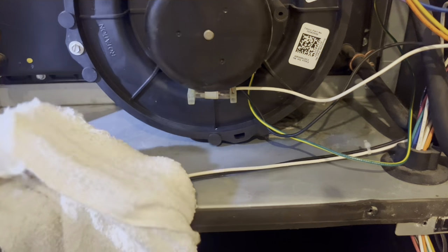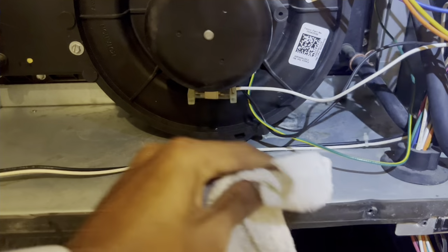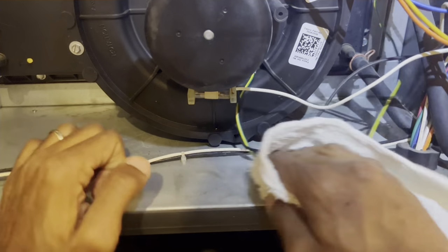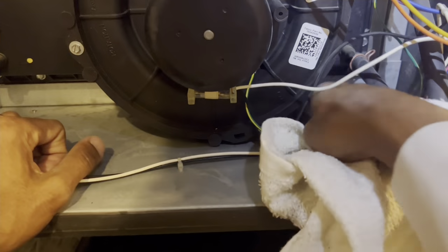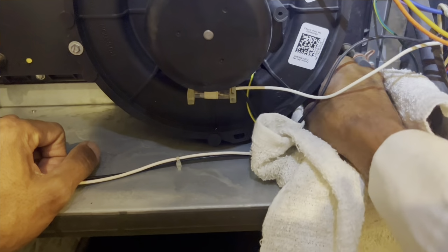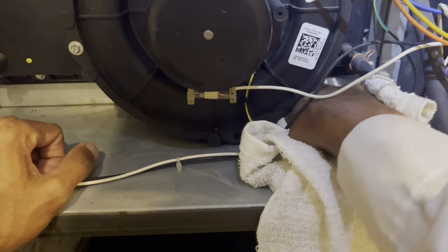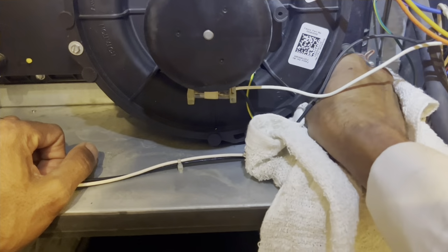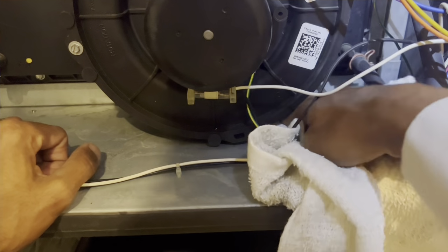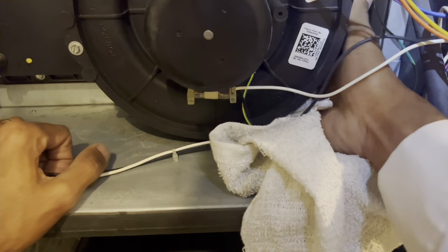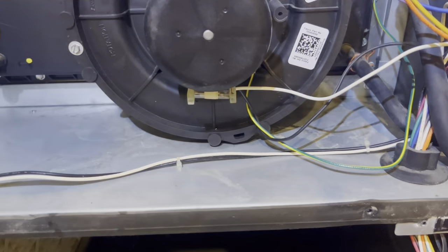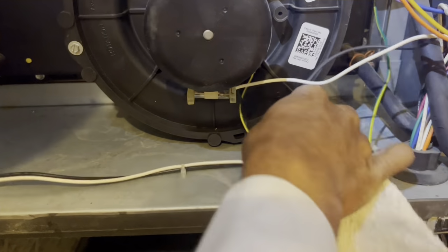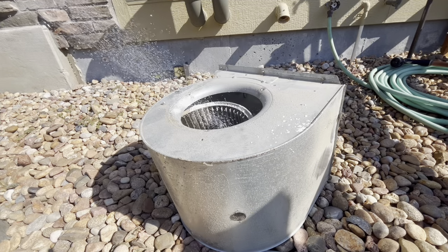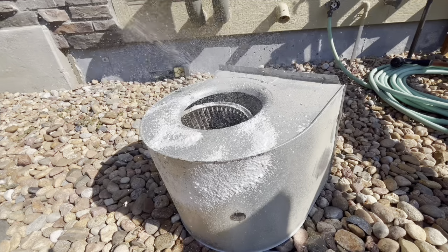Underneath this exhaust motor, this inducer motor, just wiping it clean. But there was a spot where the collector box gasket was leaking, the gasket from the collector box to the actual inducer motor. Sometimes it's a rubber O-ring, or it could be a foam gasket, and that needed to be replaced. So that's what I was going to talk to the customer about.